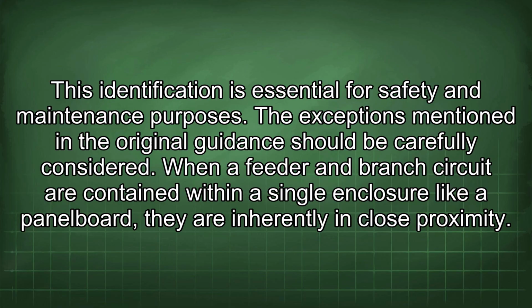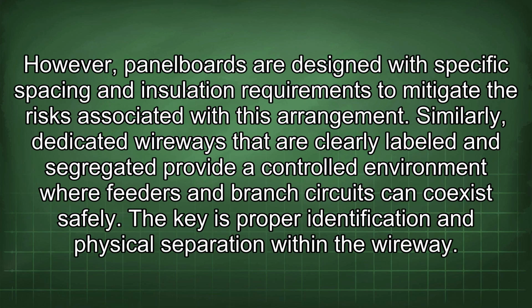The exceptions mentioned in the original guidance should be carefully considered. When a feeder and branch circuit are contained within a single enclosure like a panel board, they are inherently in close proximity. However, panel boards are designed with specific spacing and insulation requirements to mitigate the risks associated with this arrangement. Similarly, dedicated wireways that are clearly labeled and segregated provide a controlled environment where feeders and branch circuits can coexist safely. The key is proper identification and physical separation within the wireway.